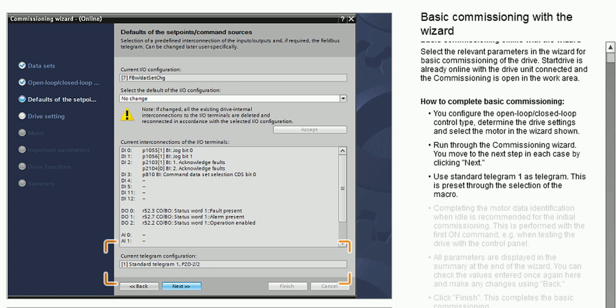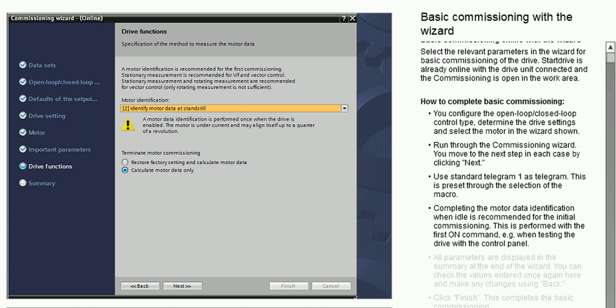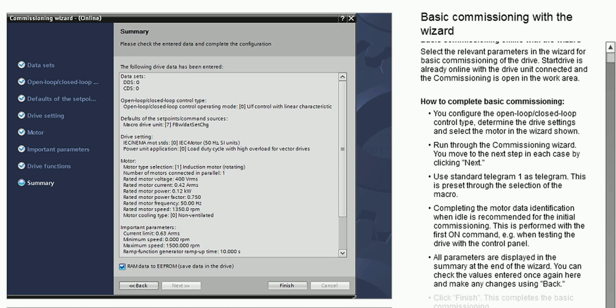Use Standard Telegram 1 as Telegram. This is preset through the selection of the macro. Completing the motor data identification when idle is recommended for the initial commissioning. This is performed with the first ON command, for example, when testing the drive with the control panel. All parameters are displayed in the summary at the end of the wizard. You can check the values entered once again here and make any changes using Back.